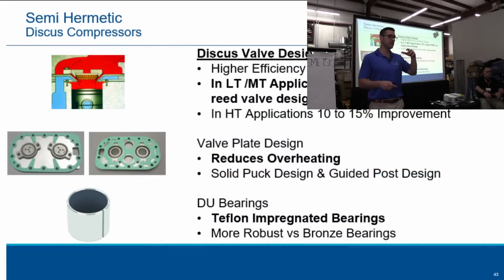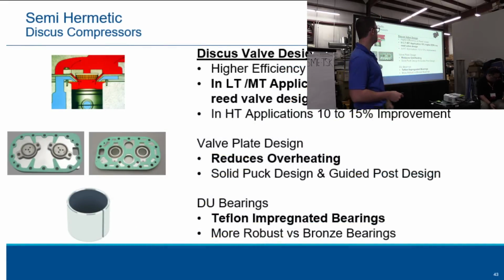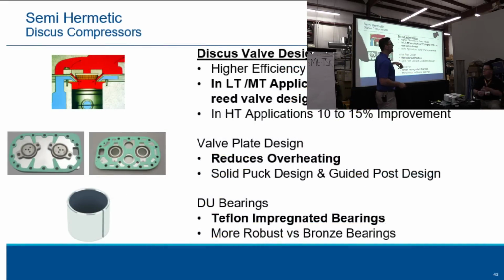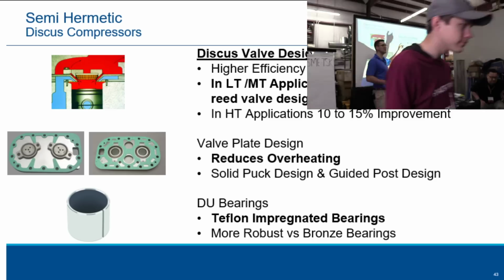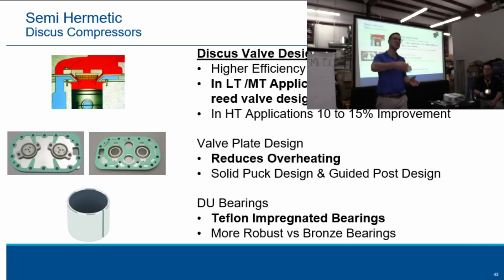Discus valve plate. So this is one of the cool things about the difference between our reed and our discus. They're higher efficiency than our reed, right? In low and medium temp application, up to 15% higher EER than the reed design. So what value is that to your customer now?